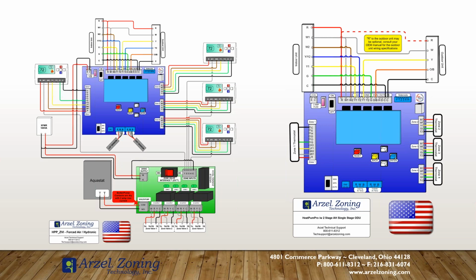Okay, so with the ZVI control, we can incorporate hydronics with a forced air system. And while it looks to be complicated because you've got wires going every which way, it's really not once you break it down. It's just a call for W1, W2. With the Heat Pump Pro being able to control 4 stages of heat with a single stage call for W, the W2 from your thermostats goes to the zoning panel. The W1 from your thermostats goes to the ZVI.